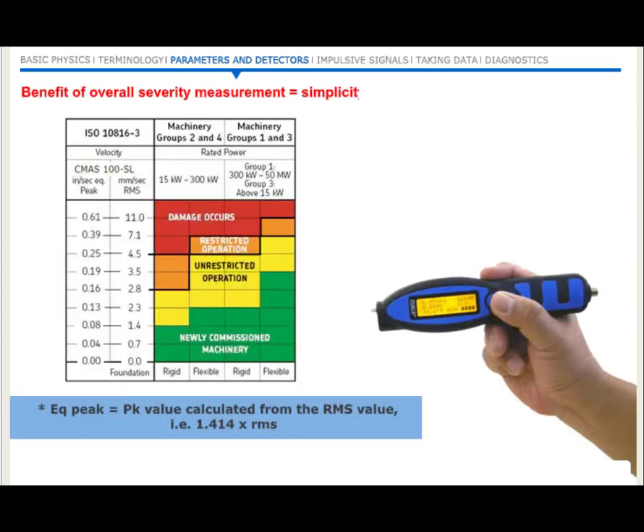A lot of condition monitoring activity relies on periodic or continuous measurements of the overall vibration level. Indeed, ISO standard 10816-3 defines areas of vibration severity according to overall levels of vibration velocity. This approach to condition monitoring has the advantage that it can be applied with relatively simple, inexpensive instruments and systems, and it works on the basis that if the total vibration does not change, then it's a reasonable assumption that the individual vibration components have stayed the same.